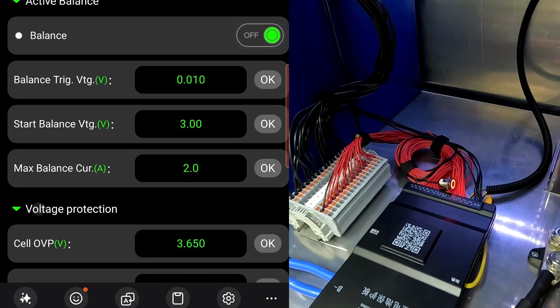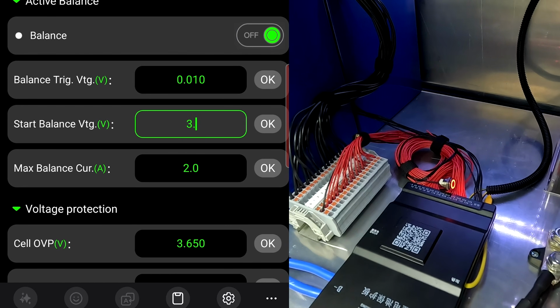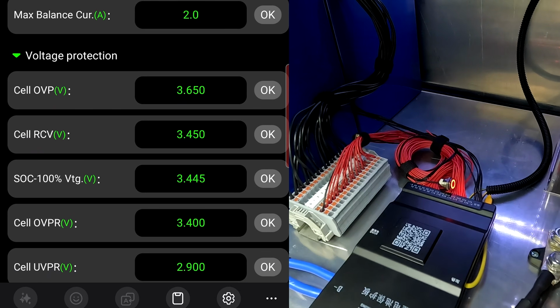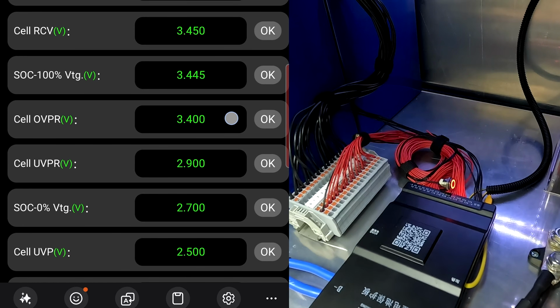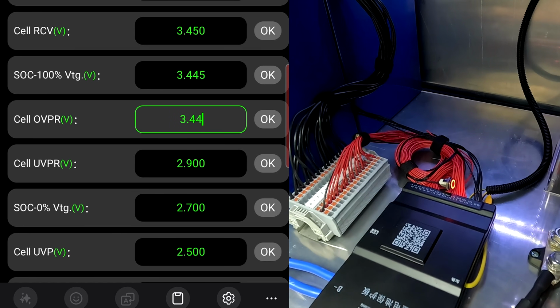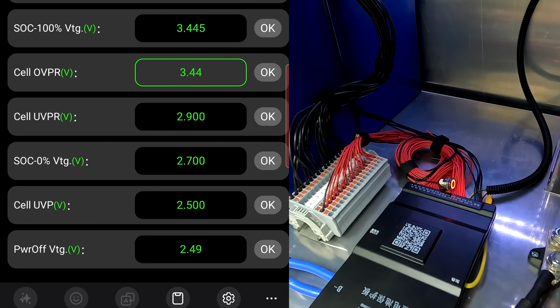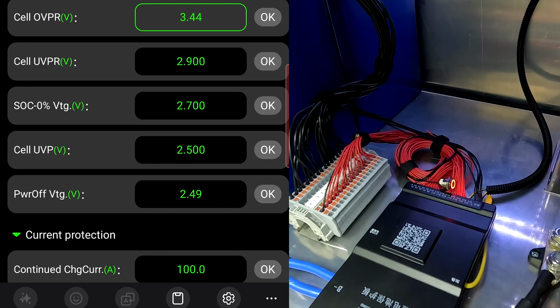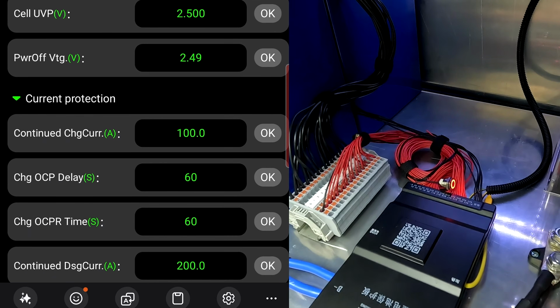I think everything is pretty much set up as per my defaults, except the balance start voltage is too low at 3 volts only. 3.65, RCV 3.45, reset at 3.445, recovery - yeah, could be a bit higher. Undervoltage protection 2.5, 2.7, it shows 0, and power off at 2.49.